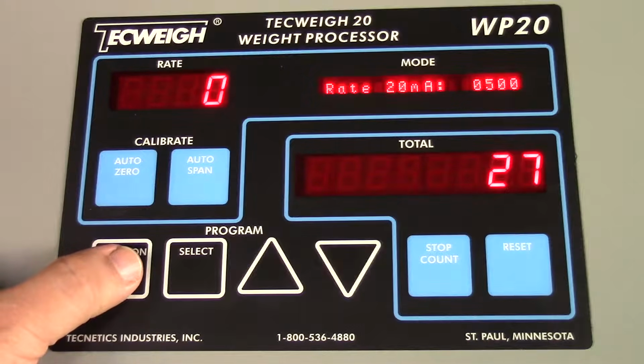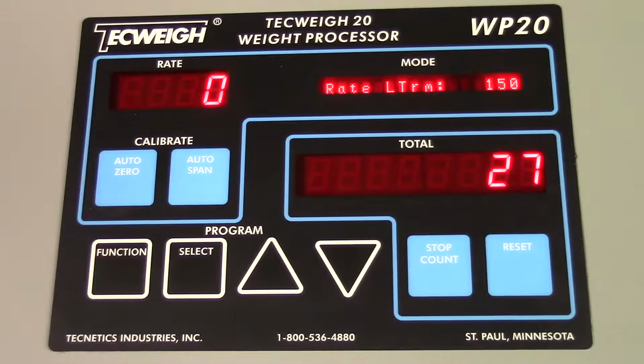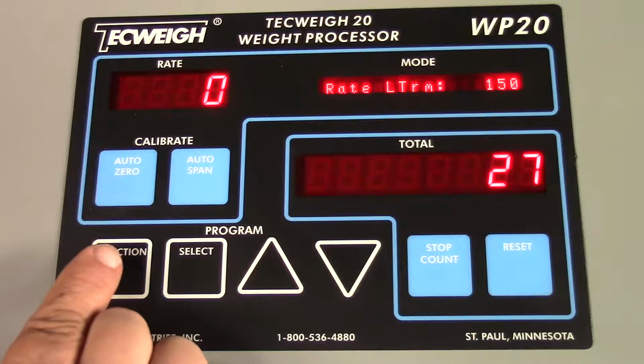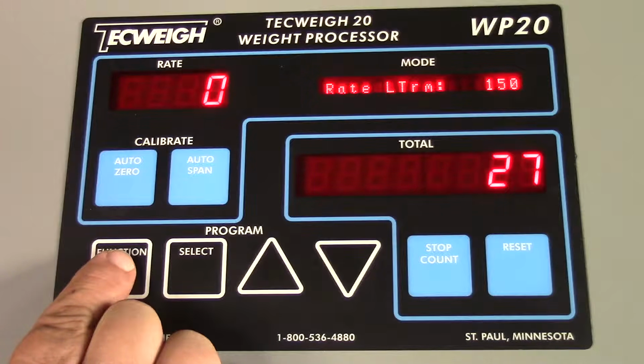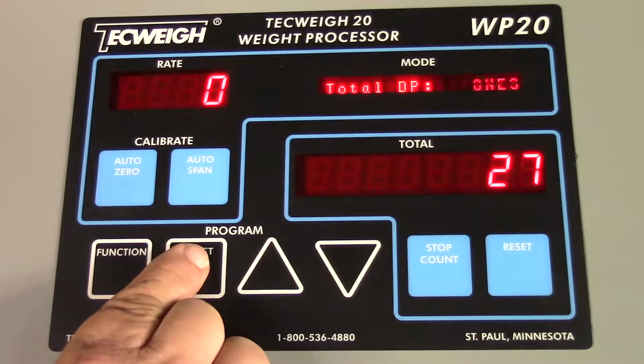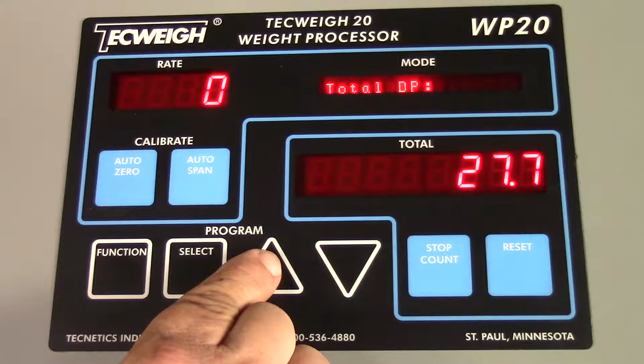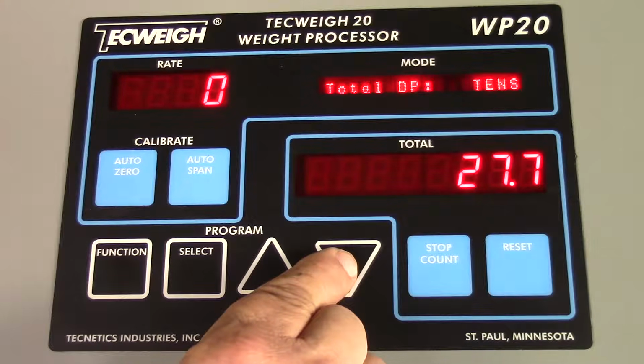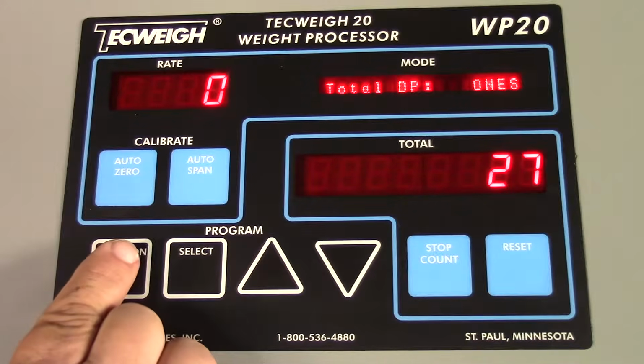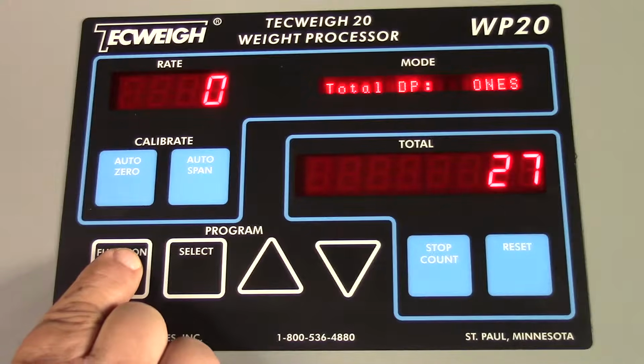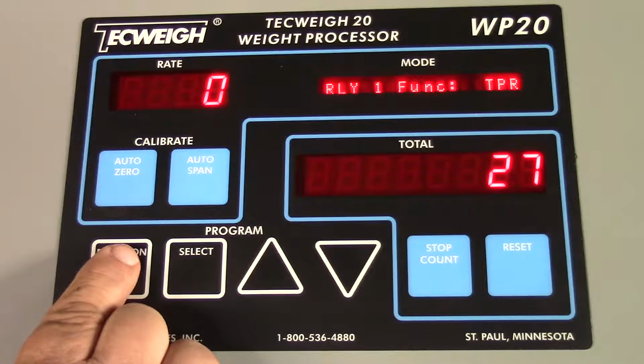of 20 milliamps. Now here's where we can set the low rate trim to adjust the 4 milliamp in order to account for line loss. It's just a very handy tool to have, as well as to be able to adjust for line loss for the 20 milliamp output. Here we can set the total decimal places. Right now it's currently set at ones, but if we set it at tens, you'll see that now we have 27.7 tons showing on the display on the totalizer. But normally we'll just leave that at ones for most applications. But it is available to change.